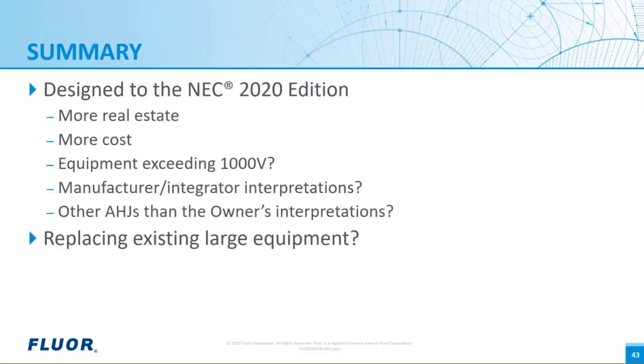So the intent, obviously, that we've been talking about today of this change was good. I love it. Especially if I were out there still carrying tools, I want all the room I can get. And as we all know, safety is priority number one, not only here at Fluor, but all companies. We want to keep our folks safe. The result of this change, however, will require more real estate for new substation buildings and electrical rooms where you have large low voltage equipment. I've looked at several different scenarios, and the increase can range anywhere from 10 to 15 to 20% larger due to this rule.